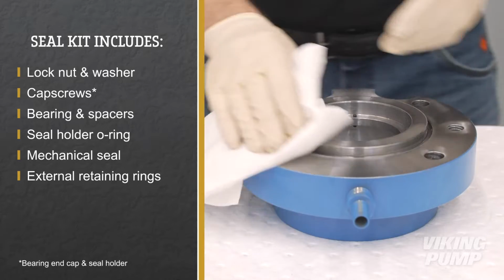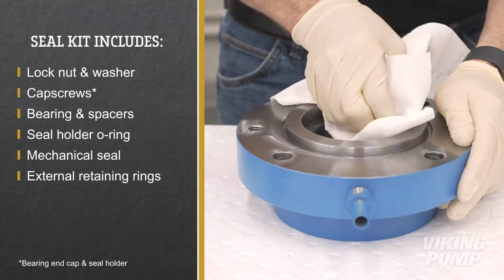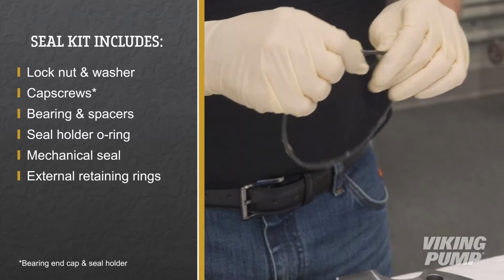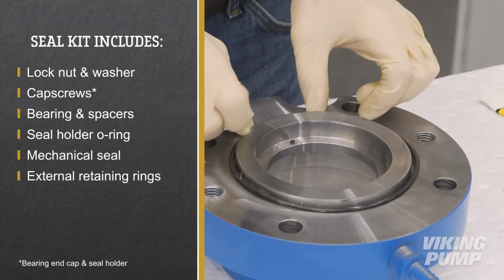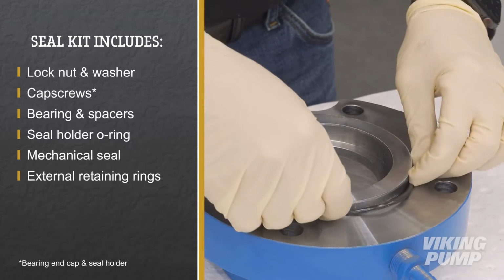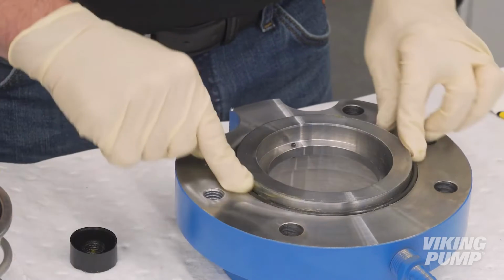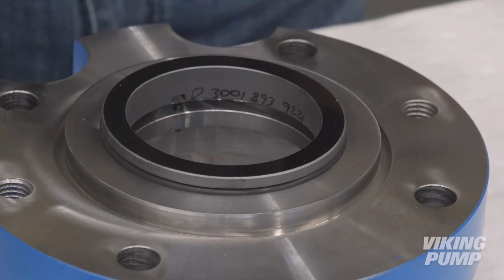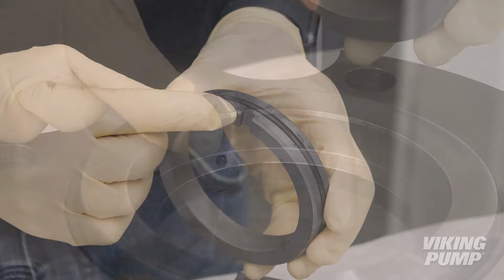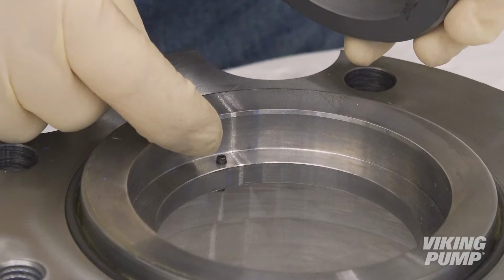It is now time for the seal installation. Begin by cleaning the seal holder assembly thoroughly. Apply O-ring grease to the seal holder O-ring and place in the groove. Next, install the stationary seat into the seal holder assembly. Make sure to line up the notch with the pin in the face of the seal holder assembly.